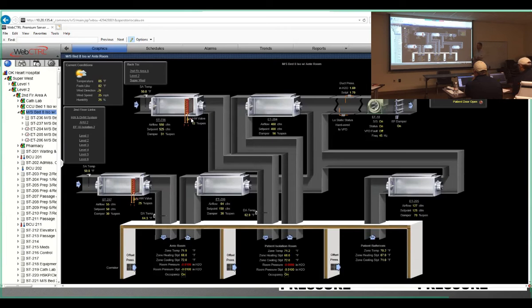I think some of these limits, where we change these colors, we're going to have to adjust, because it's really tight. It's showing red when you're actually only 1/1000th of a difference, so I don't think it's bad. Or we bump those up to .012 as well, right? So just make sure we stay above the point, because those are nuisance alarms. This, I think, is just a visual thing. It's not necessarily an alarm. Well, yes, it is, I'm sorry.